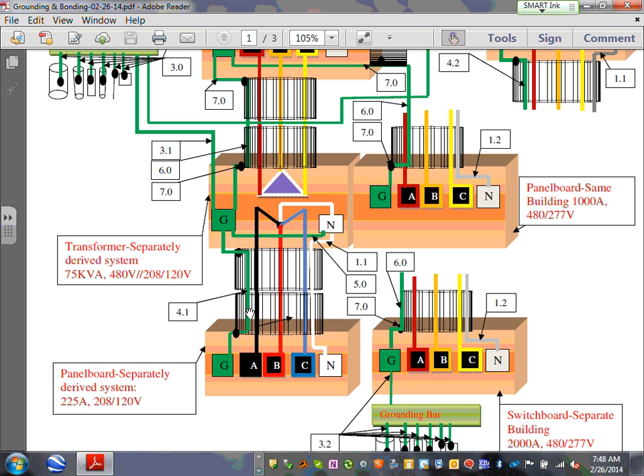The amps and the voltages are so important, because when we do grounding and bonding, we're going to take the amps, the voltages and all these things into consideration. So that's a branch circuit going to a transformer to feed a receptacle panel. That's a typical grounding and bonding. The reason I picked this scenario for you guys is that it's called a separately derived system. We're going to talk about separately derived systems, and grounding and bonding for it is unique by the code.